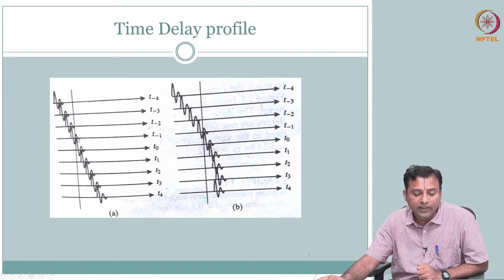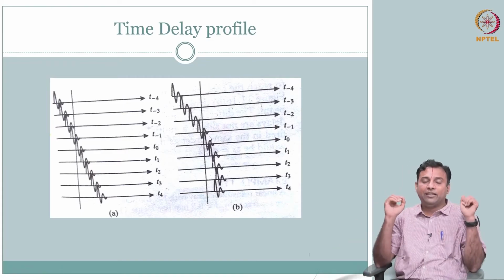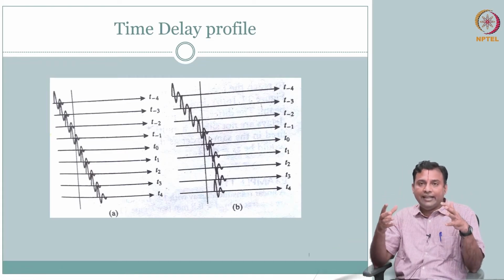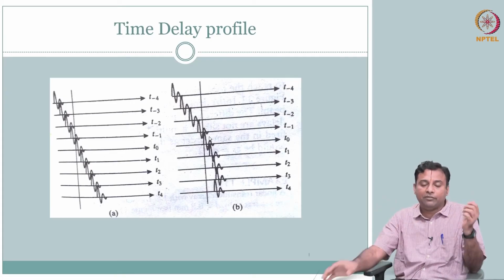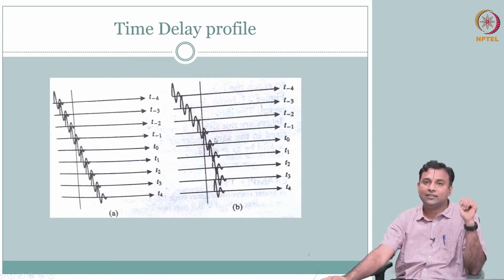Steering alone is only linear with respect to each of the elements; the time delays are just multiplied, whereas here that is not the case. Okay. So, this is for transmit. I have sent the wave in a direction I want with a specific focus. I have sent it. Now, what do you do? So, this is your transmit beam forming, if you will.